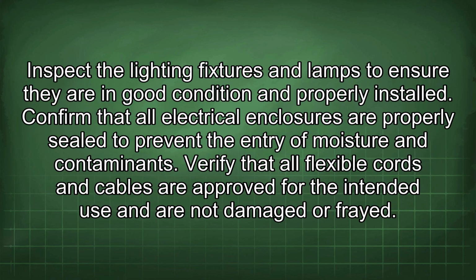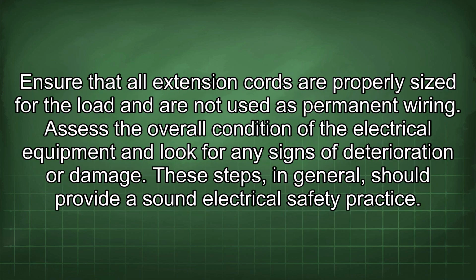Inspect the lighting fixtures and lamps to ensure they are in good condition and properly installed. Confirm that all electrical enclosures are properly sealed to prevent the entry of moisture and contaminants. Verify that all flexible cords and cables are approved for the intended use and are not damaged or frayed. Ensure that all extension cords are properly sized for the load and are not used as permanent wiring. Assess the overall condition of the electrical equipment and look for any signs of deterioration or damage. These steps, in general, should provide a sound electrical safety practice.